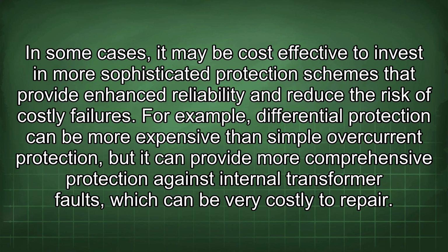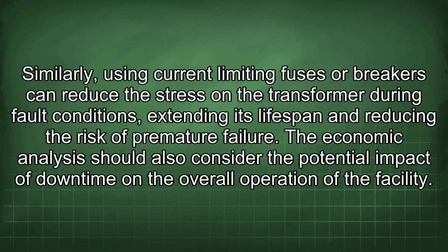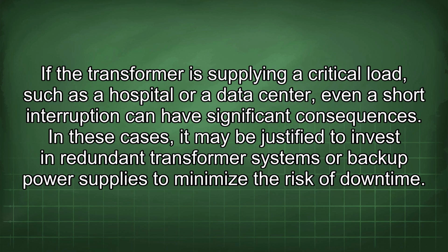For example, differential protection can be more expensive than simple overcurrent protection, but it can provide more comprehensive protection against internal transformer faults, which can be very costly to repair. Similarly, using current-limiting fuses or breakers can reduce the stress on the transformer during fault conditions, extending its lifespan and reducing the risk of premature failure. The economic analysis should also consider the potential impact of downtime on the overall operation of the facility. If the transformer is supplying a critical load, such as a hospital or a data center, even a short interruption can have significant consequences. In these cases, it may be justified to invest in redundant transformer systems or backup power supplies to minimize the risk of downtime.